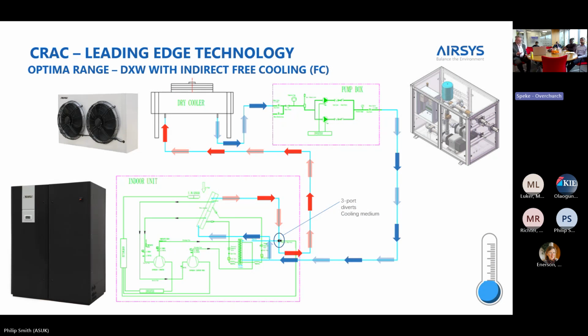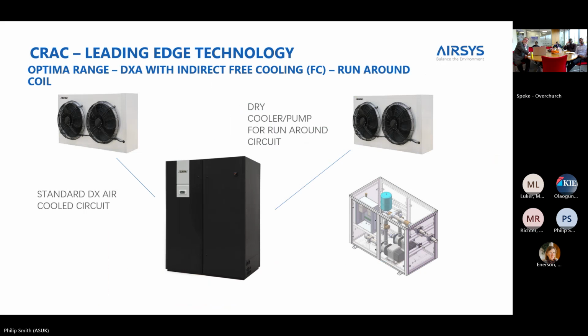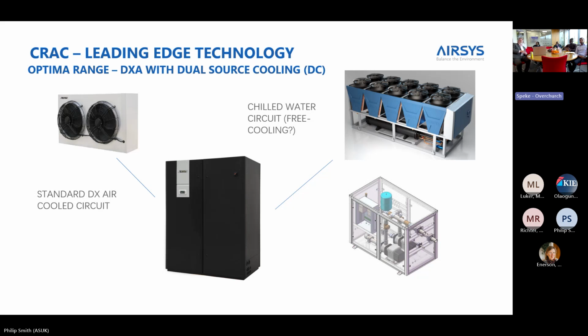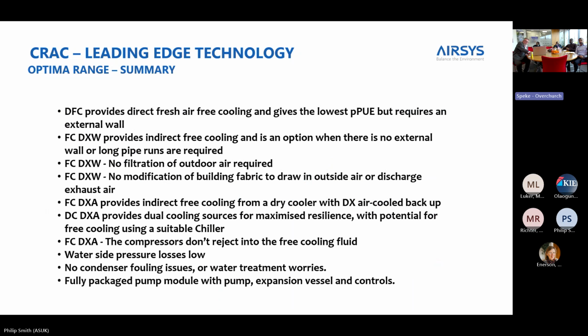inside the unit. So the refrigerant is a tenth of what it might be typically for a standard air-cooled unit. You could go one further, and you could put a permanent run-round coil with separate planting, and then additional pipework, etc. Or you could even put a free cooling chiller on the other circuit, and then have dual redundancy of refrigerant, etc. Again, you've got the facility then to bring in free cooling.